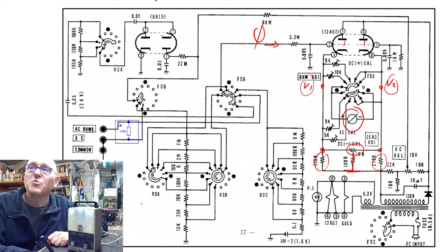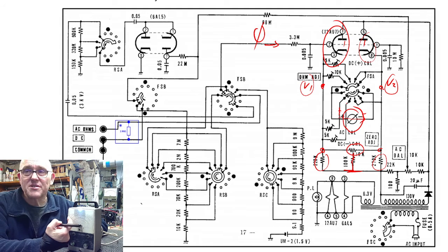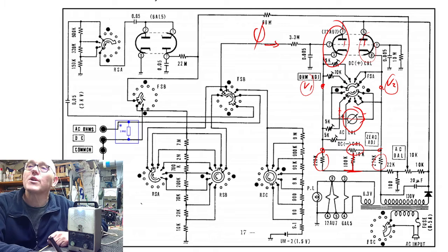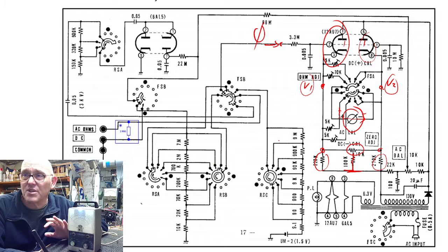Now when I take an input voltage, I will upset the balance of voltages at this point, because now this portion of the triode will conduct more than this portion. This voltage will begin to increase, that voltage will begin to decrease, and it will actually amplify the difference between these two circuits. I'll get an increased voltage sitting over here, I'm getting a lower voltage over there, and now I'll start to pass current through my meter, and my needle will rise according to the amount of voltage presented at the input. That is the way this meter circuit works.